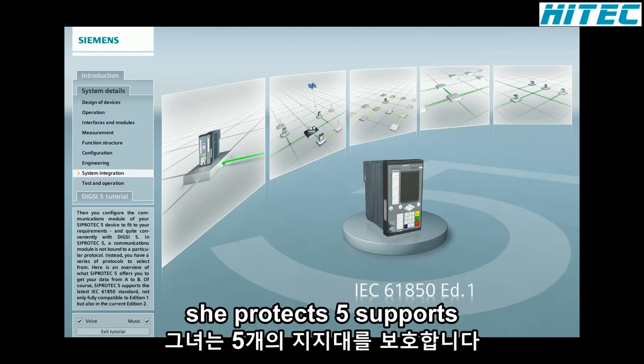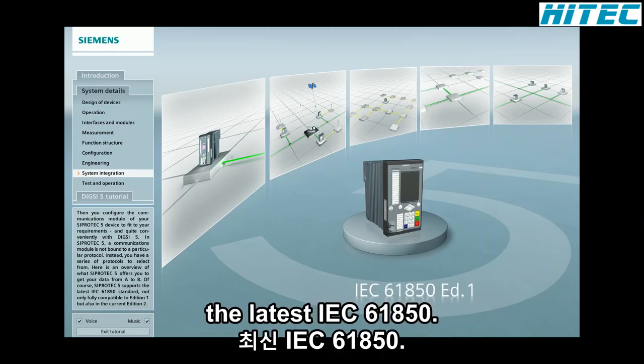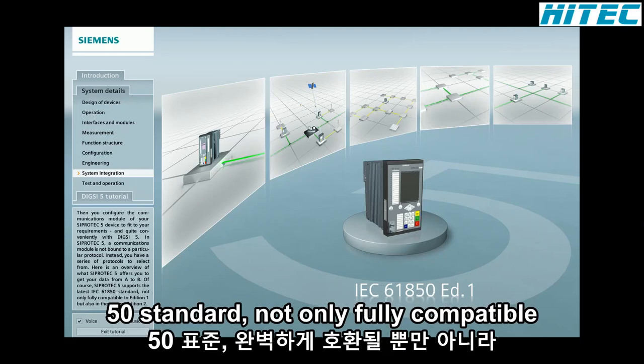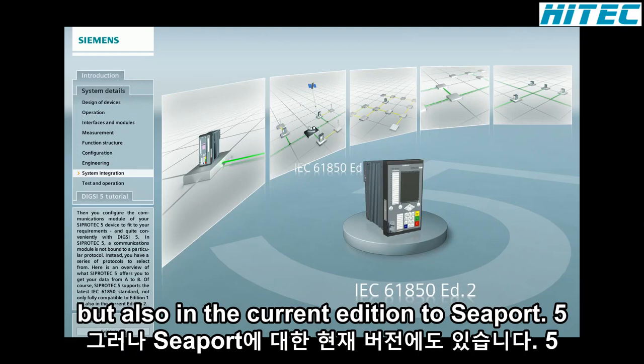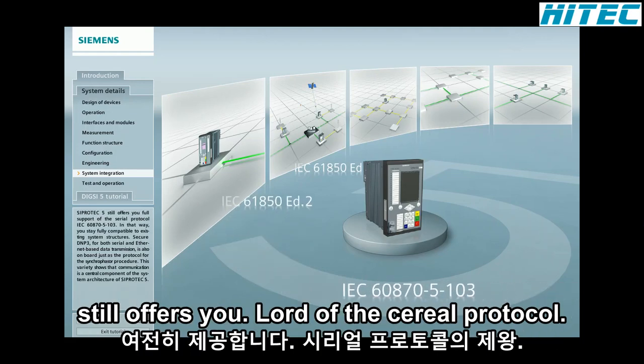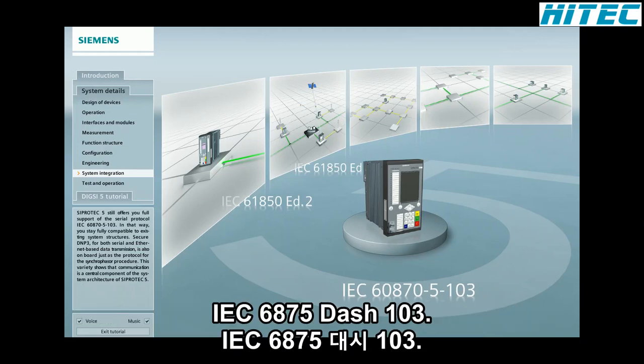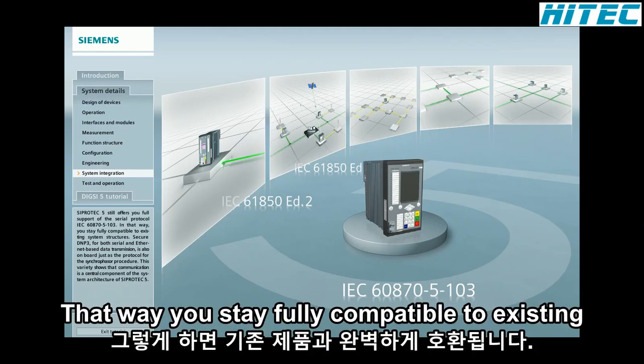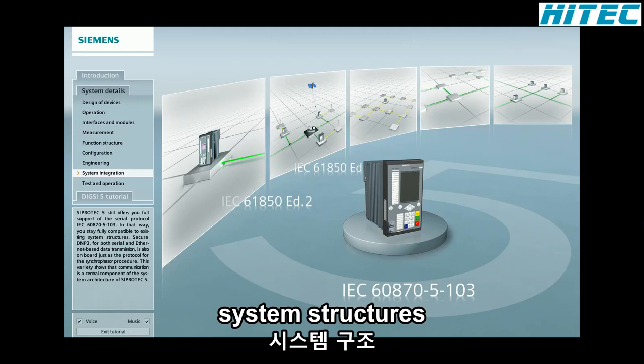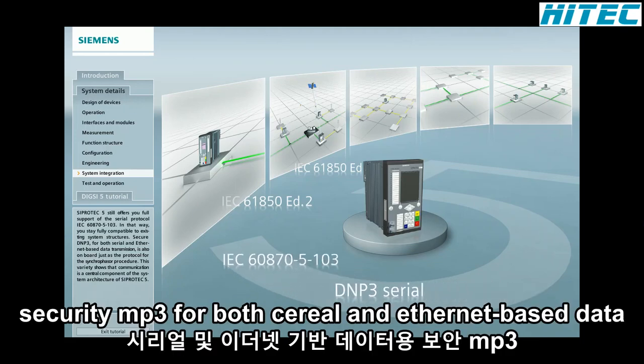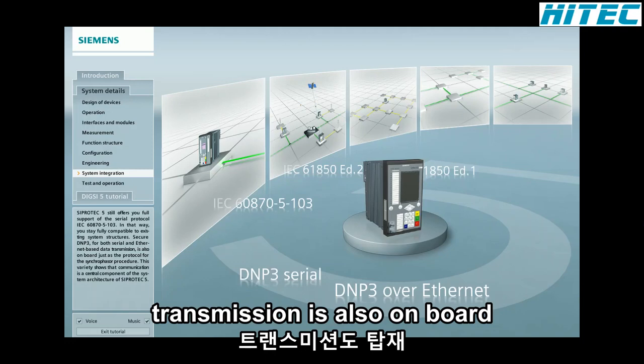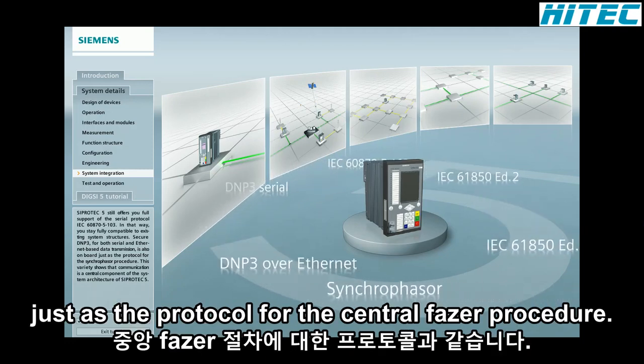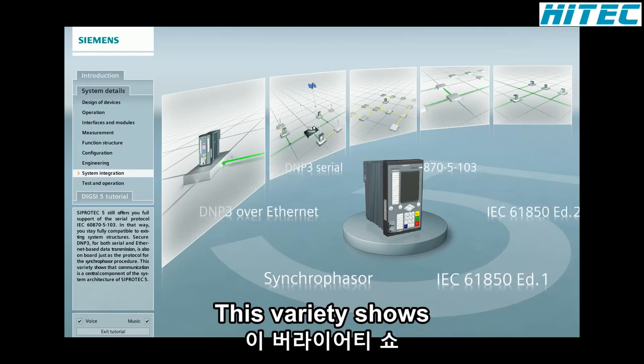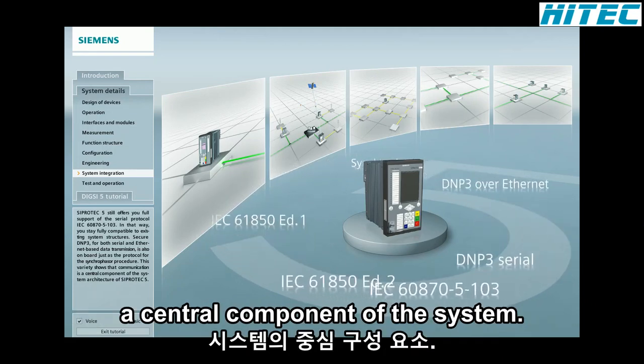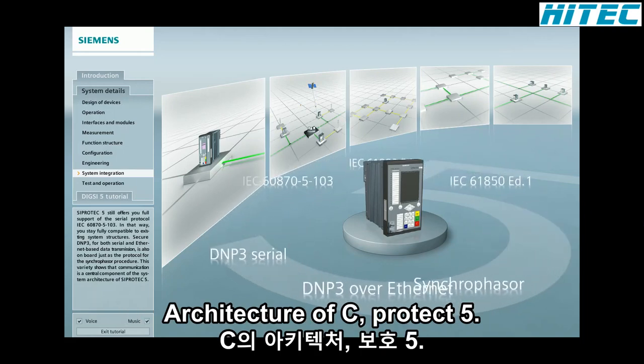Of course, SIPROTEC 5 supports the latest IEC 61850 standard, not only fully compatible to Edition 1, but also in the current Edition 2. SIPROTEC 5 still offers you full support of the serial protocol IEC 60870-5-103. That way, you stay fully compatible to existing system structures. Secure DNP3 for both serial and Ethernet-based data transmission is also on board, just as the protocol for the synchrophasor procedure. This variety shows that communication is a central component of the system architecture of SIPROTEC 5.